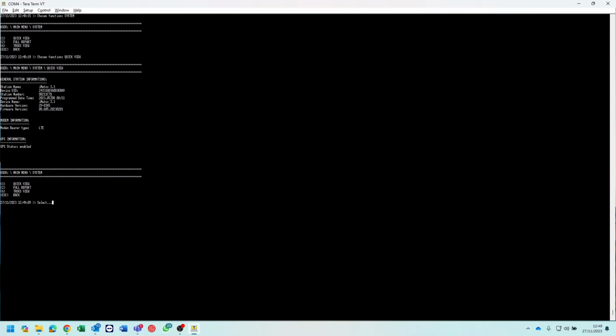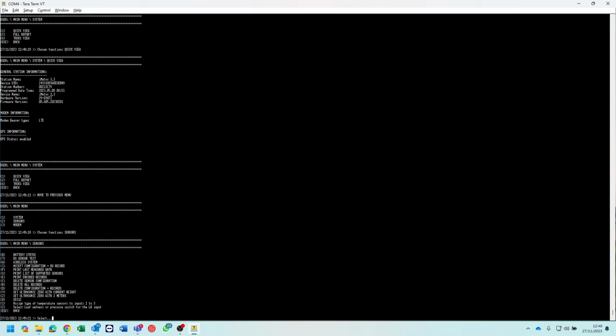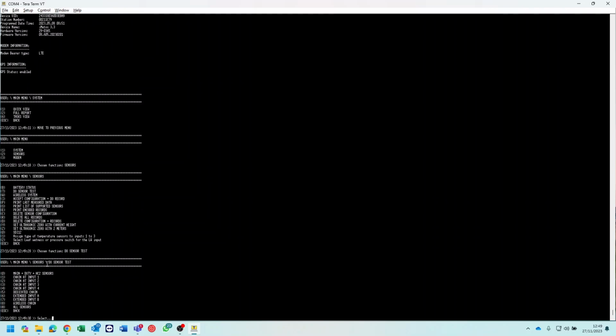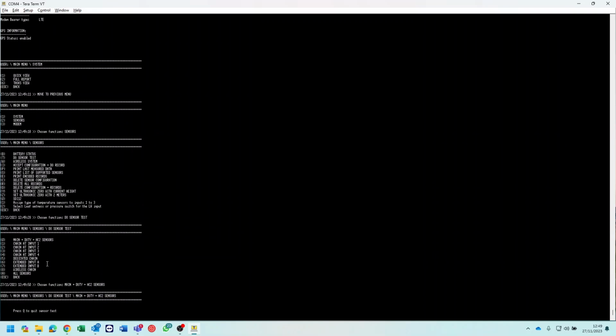I'm going to escape out of there, and I'm now going to go down to sensors to show you how to check sensors that are connected to your DTU. To do a sensor test, we need to hit the letter T, just here, do sensor test. Once I hit that letter T, we've got a number of options coming up. Option 0 is the main one to test the solar panel, if that's working correctly, what energy that's putting into your battery, the battery power levels, voltage-wise, and if you've got rain tippers attached, that will also appear on the list here. So I'm going to hit number 0.